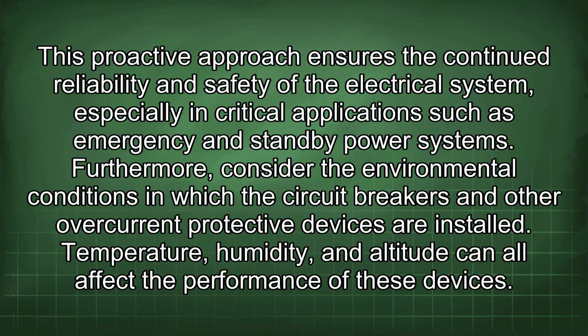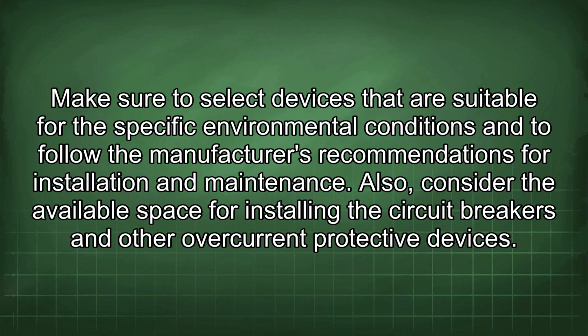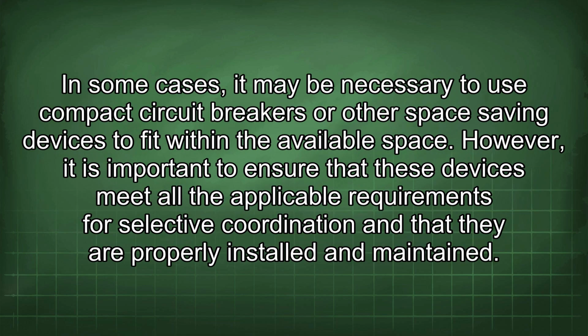Furthermore, consider the environmental conditions in which the circuit breakers and other overcurrent protective devices are installed. Temperature, humidity, and altitude can all affect the performance of these devices. Make sure to select devices that are suitable for the specific environmental conditions and to follow the manufacturer's recommendations for installation and maintenance. Also, consider the available space for installing the circuit breakers and other overcurrent protective devices. In some cases, it may be necessary to use compact circuit breakers or other space-saving devices to fit within the available space.